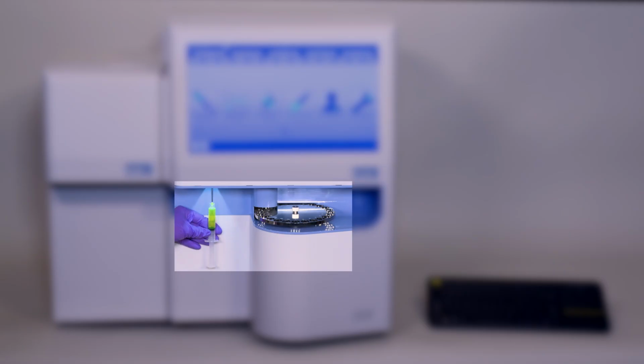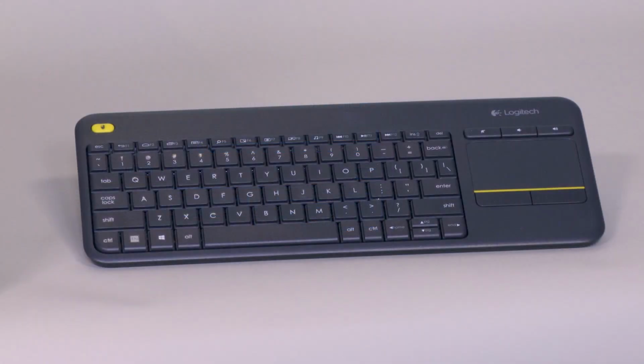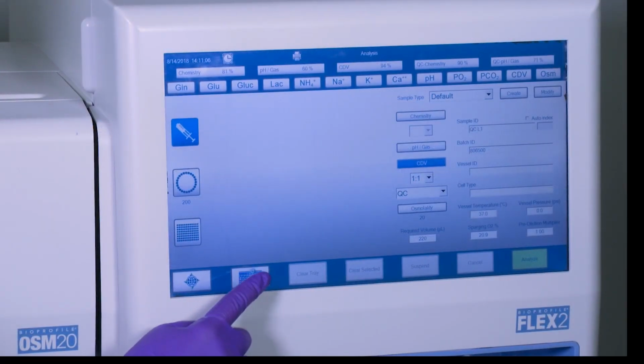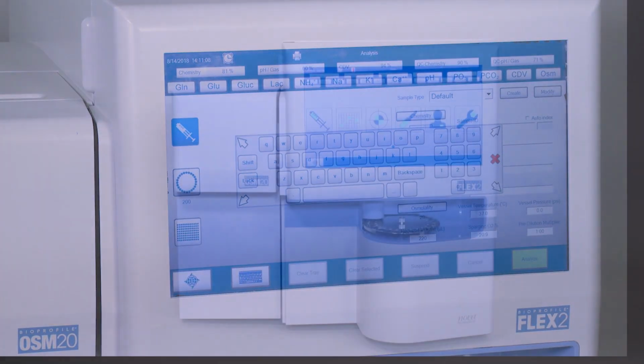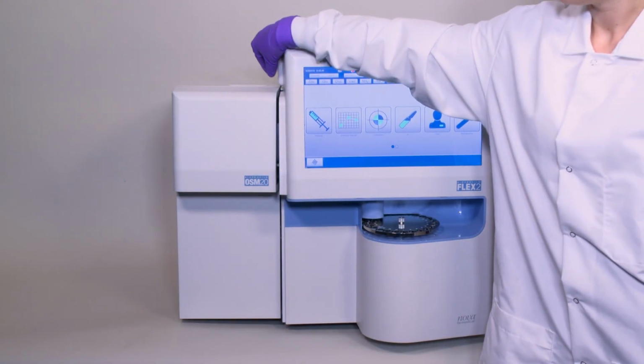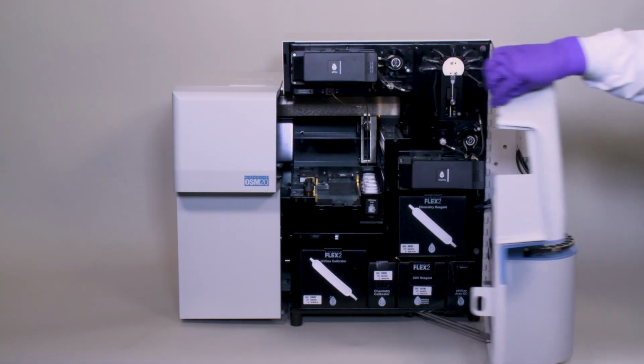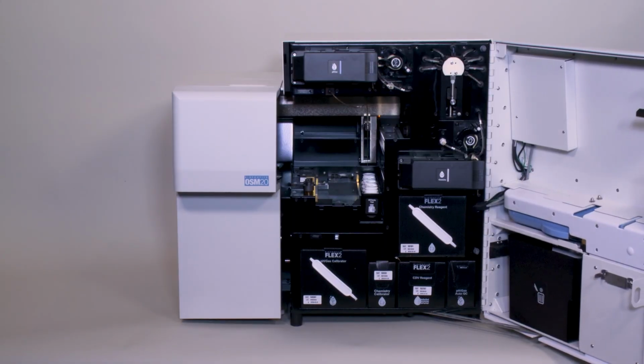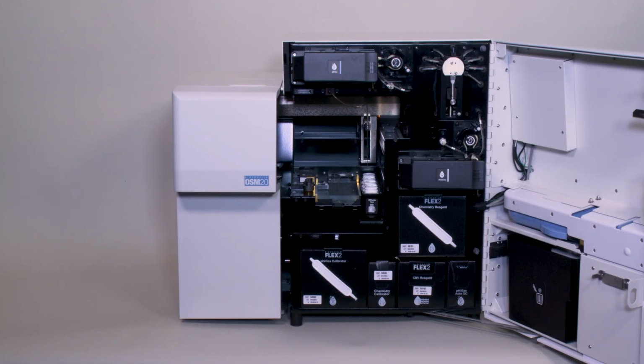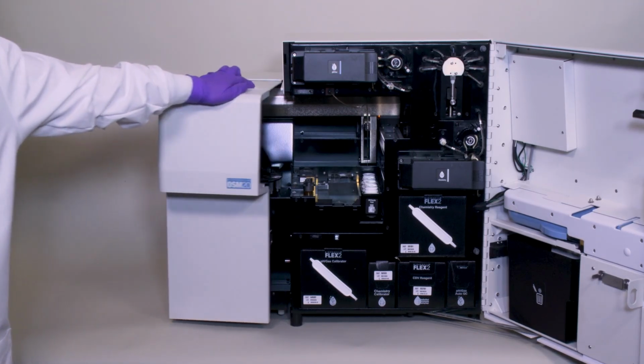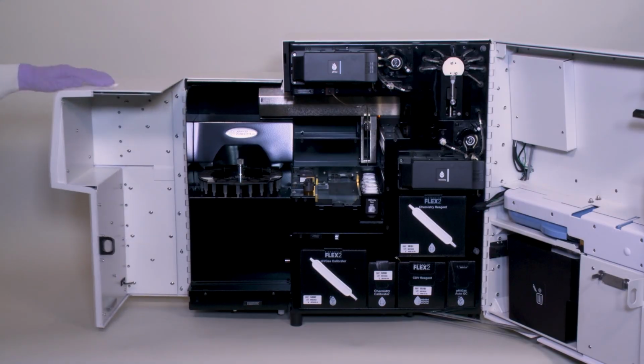Here, a light will illuminate, and the probe will come out to aspirate your sample. There is a wireless keyboard with a mouse pad to allow you to enter information, or you can use the on-screen keyboard and touchscreen. The analyzer door can be opened from the right side of the analyzer to access the components inside. FLEX 2 systems with the optional osmometer module will have a slightly larger footprint than systems without. In addition, systems with the osmometer will have a smaller front door panel on the left, which opens to access the osmometer module carousel.